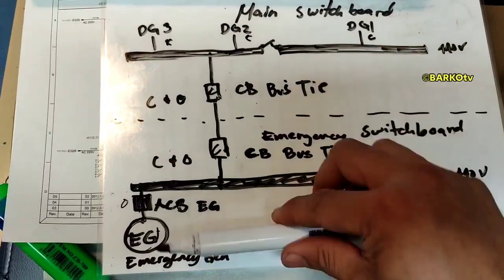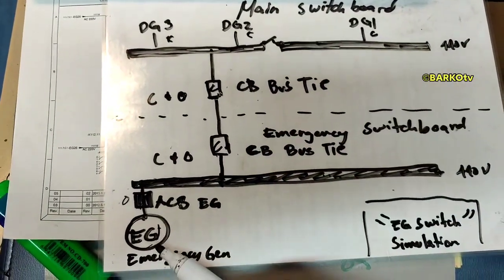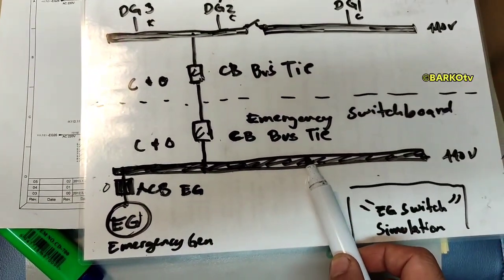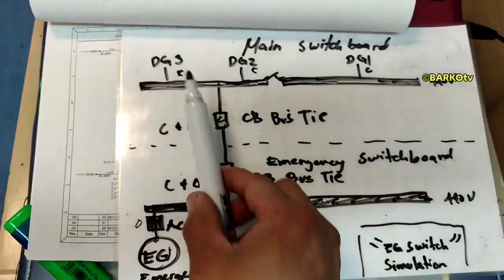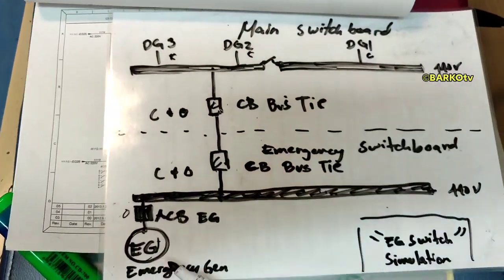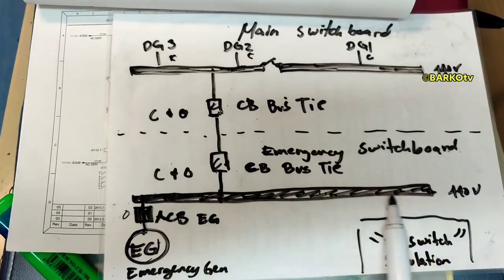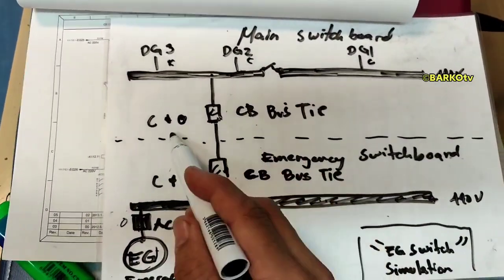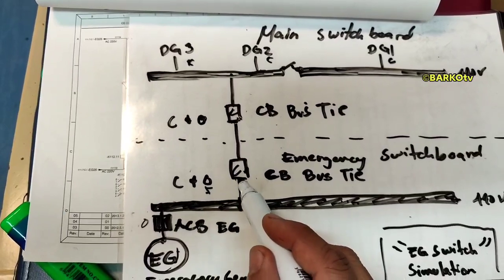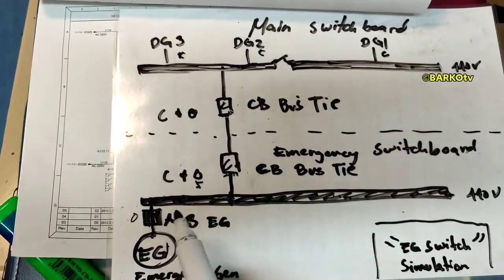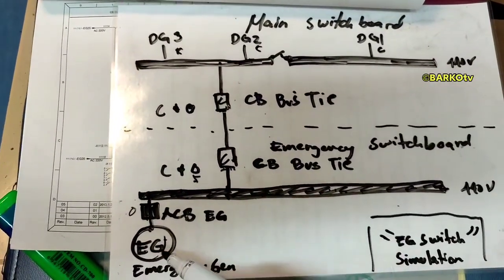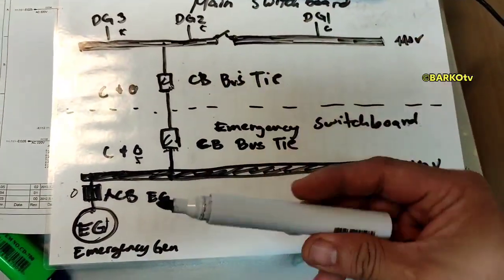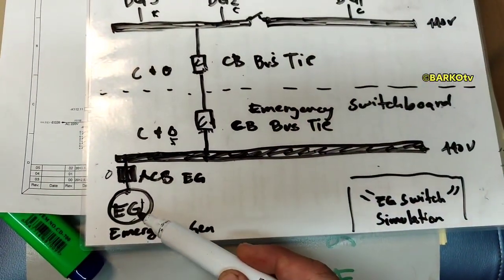The emergency generator supplies the emergency switchboard in isolated mode. In normal operation, the main switchboard supplies the emergency switchboard because the emergency generator is turned off. In the next scenario, if you open the bus tie on the other side, the same sequence occurs — you have isolated the main switchboard from the emergency switchboard.